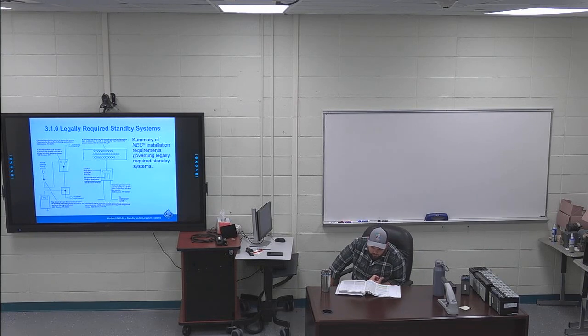Moving on. Last paragraph on page 20, first sentence is highlighted. Current must be supplied to legally required standby systems so that in the event of a normal power failure, legally required standby power will be available within the time required for the application, but not to exceed 60 seconds. So these systems have to come on within 60 seconds. That's what you want to key in on for these legally required standby systems.